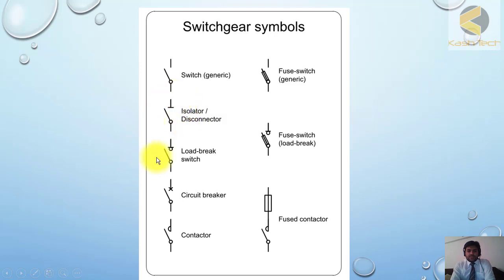This one is load break—it means you can break the current manually, but you don't have any sensing device which can sense high current and trip. This is a circuit breaker which can break the current—it has tripping and closing coils at 132 kV levels. This is a contactor.